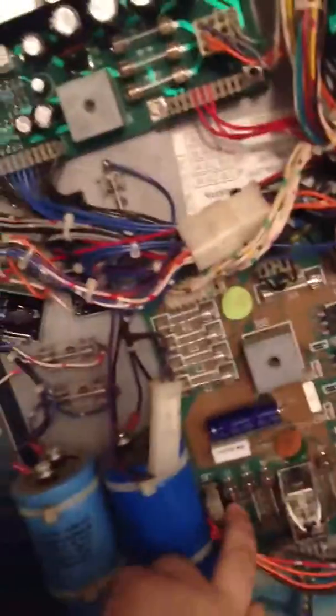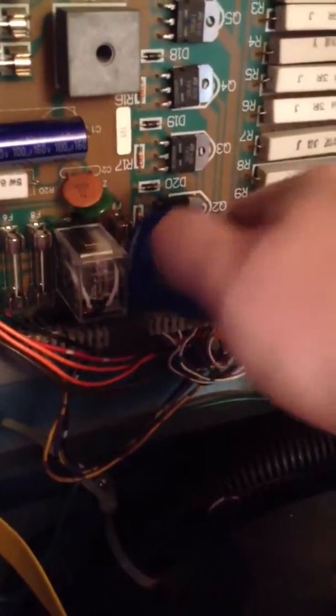The temperature of the fuse also started going down. I've had it cycling for a good while and it still feels kind of warm to the touch — about 90 degrees. It was showing 90.1 when I pulled it off, so definitely a lot less hot than it was before. Most of the other fuses are running around the 70s or so, so it's still warmer.